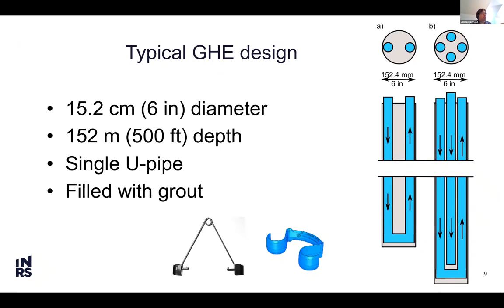Typical design for ground heat exchangers, at least for boreholes we install in Canada, I'm not sure in Colombia how the systems were designed and installed. But typically it's a 6-inch diameter borehole, or 15 centimeters if you prefer, drilled with rotary drilling technology. The depth is about 150 meters, roughly 500 feet, and most of the time what is installed is a single U-pipe to flow the fluid that makes the heat transfer with the ground.